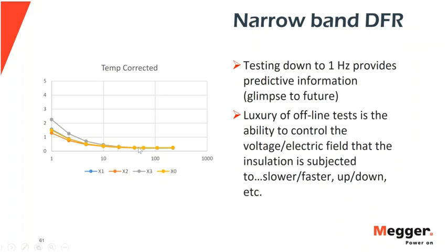Okay, but how do I want to treat a trend happening in power factor going forward? Well, I'd probably be more apt to respond with great alarm if my X3 power factor at 60 hertz starts to trend high versus some of these others, given this extra predictive information.